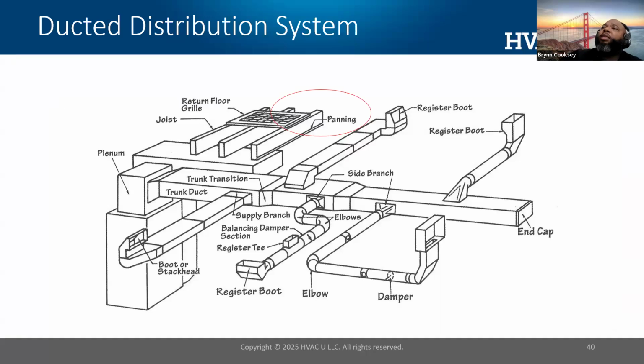And here's a problem. For the same reason as the load calc, if I put in a heat pump and I don't evaluate the duct system, I can be setting myself up for issues also, especially when the ducts are located in an unconditioned space. If you have ducts in the attic or crawl space and they're not properly sealed, sized, and insulated, that low discharge temperature of the heat pump is going to be eaten by the heat loss to the ambient air. So as a result, you have even more homework to do when heat pumps are on the table for a customer. And the duct system should be evaluated to ensure that not only is the load sized properly, the ducts can handle often the additional amount of airflow needed for a heat pump.